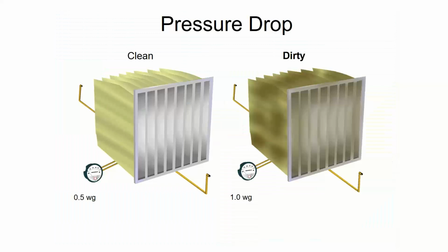When should you change these filters, right? Because I said airflow and pressure drop are a big deal. You should measure the differential pressure across the filter and compare it to the specs of that filter to know when to change it. A lot of people don't do that. At your house, you probably don't do that. I do that at my house. I actually have a system that monitors that, but I'm a little bit weird. But an average homeowner wouldn't.